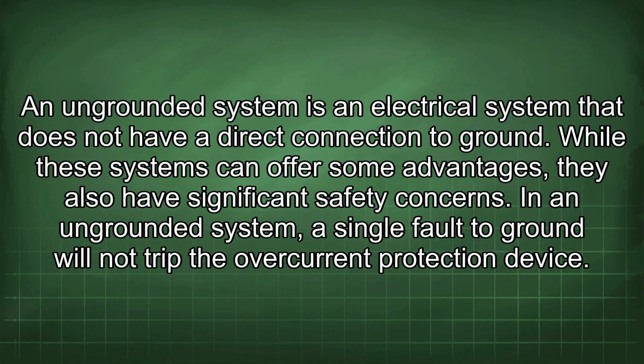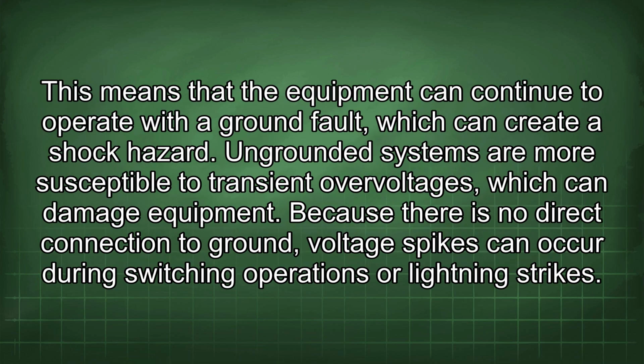An ungrounded system is an electrical system that does not have a direct connection to ground. While these systems can offer some advantages, they also have significant safety concerns. In an ungrounded system, a single fault to ground will not trip the overcurrent protection device. This means that the equipment can continue to operate with the ground fault, which can create a shock hazard. Ungrounded systems are more susceptible to transient overvoltages, which can damage equipment.